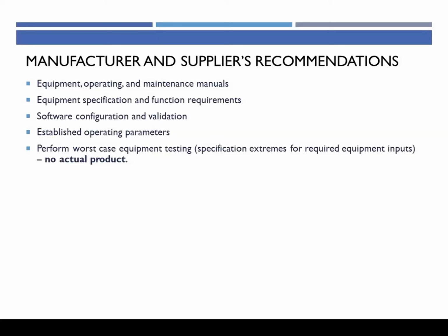So you want to get any manuals that come with it. You want to get the specifications for that equipment and make sure that matches what you ordered. You want to know what software is in there, what version or configuration level of the software is in there. You want to know what the operating parameters are for this equipment. Does it need a special foundation? Does it need to be hooked up to utilities? Make sure you meet those requirements.